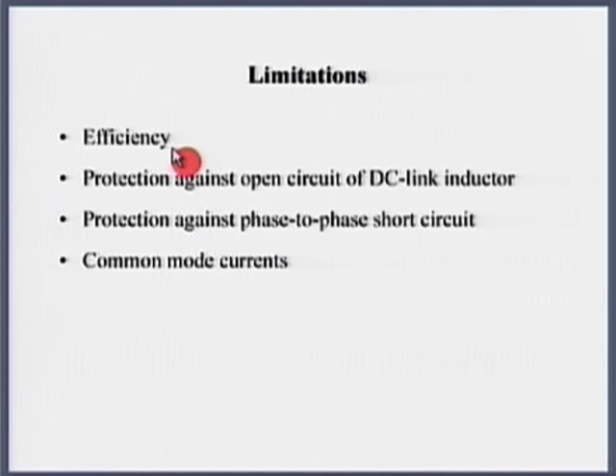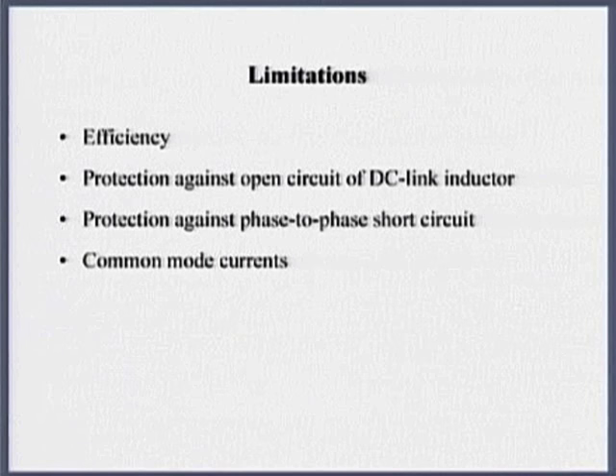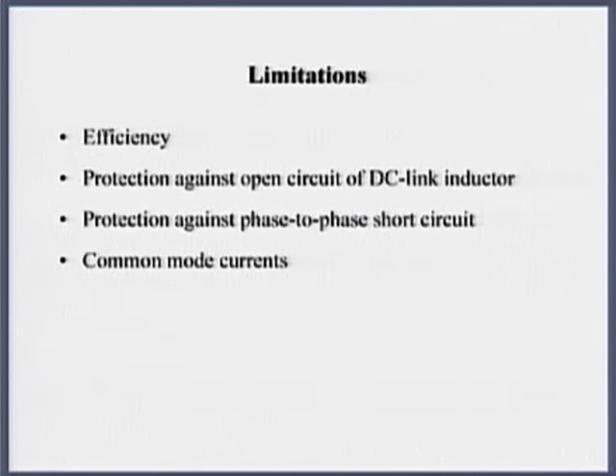Efficiency limit - efficiency is an issue here. Efficiency is slightly lower here. Protection against open circuit in the DC link inductor - you need to ensure that DC link current has to be continuous. Protection against phase to phase short circuit. If there is a phase to phase short circuit here, it is not going to be a powering mode, it is equal to energy storage mode. So you need to protect or you need to sense the phase to phase short circuit as well. And there is common mode currents, there is something similar there. That is about the current source.